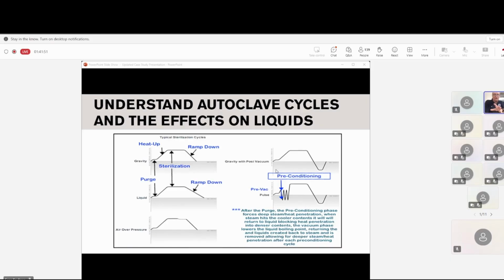On the pointer, you have your same purge section that you see in that little hump, and then it'll drive it up to 9 or 10 psi, depending on if you're running the 121 cycle. And I'm going to assume the 121. So you're running the 121 pre-vac cycle, and what it'll do is pump in about 9 to 10 psi. Now you have to remember what's going on and the physics of what's happening.